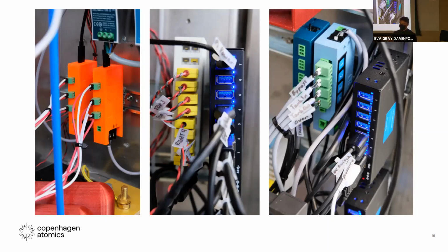So the loops are all autonomously operated. We have a programmed sequence for everything, from purging the loop at start, to heating it up, to automatically priming at a certain temperature, running for an amount of time, throttling the RPM up and down on the VFD, then depriming and cooling down. That's the same kind of operations you want to do in a reactor.